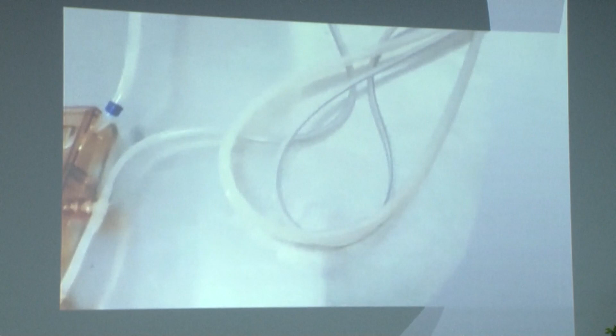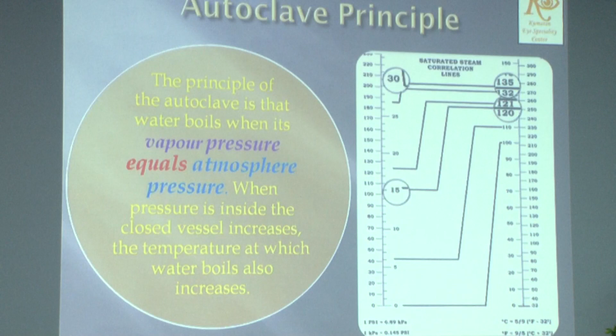So we know all about the autoclave, but you have to know a little bit more about autoclaves, because that would help you to troubleshoot whenever you have a problem. The simple principle is water boils when the vapor pressure is equal to the atmospheric pressure. So increase the pressure inside the autoclave, and the water boils at a higher temperature. This is a very simple technique.